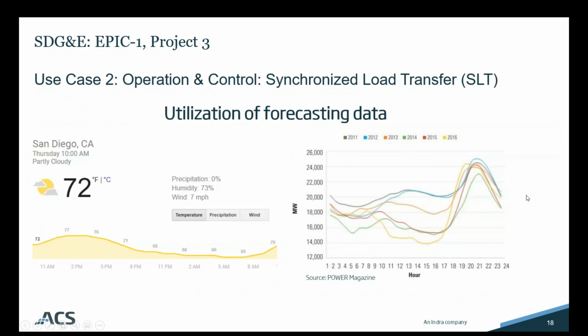So with that, moving on to use case number 2, operation and control and synchronized load transfer. The first thing we'll look at is utilizing forecasting data. So this is both weather and load data to run what we call a feeder injection test to attempt to identify any system violations prior to occurring.